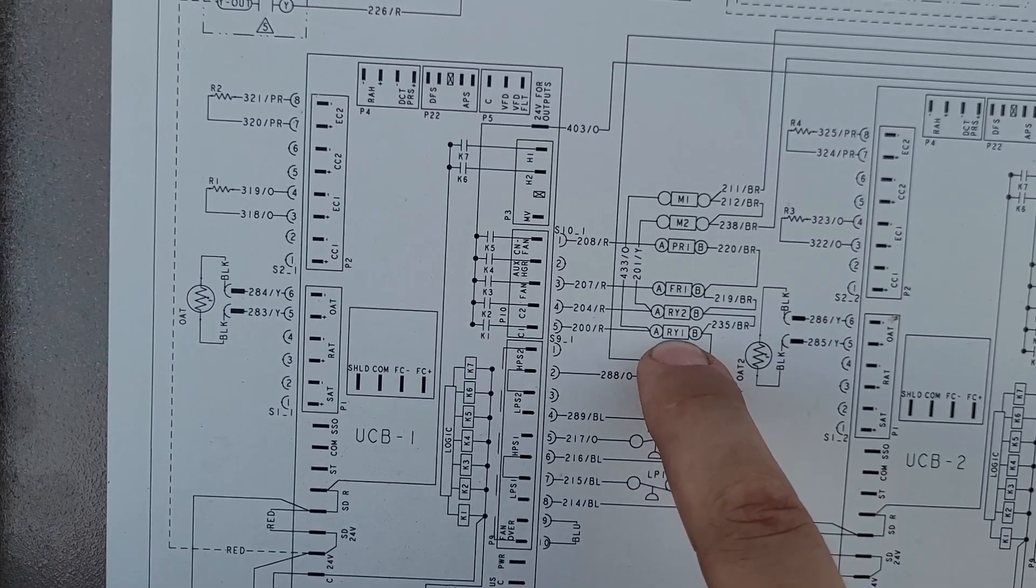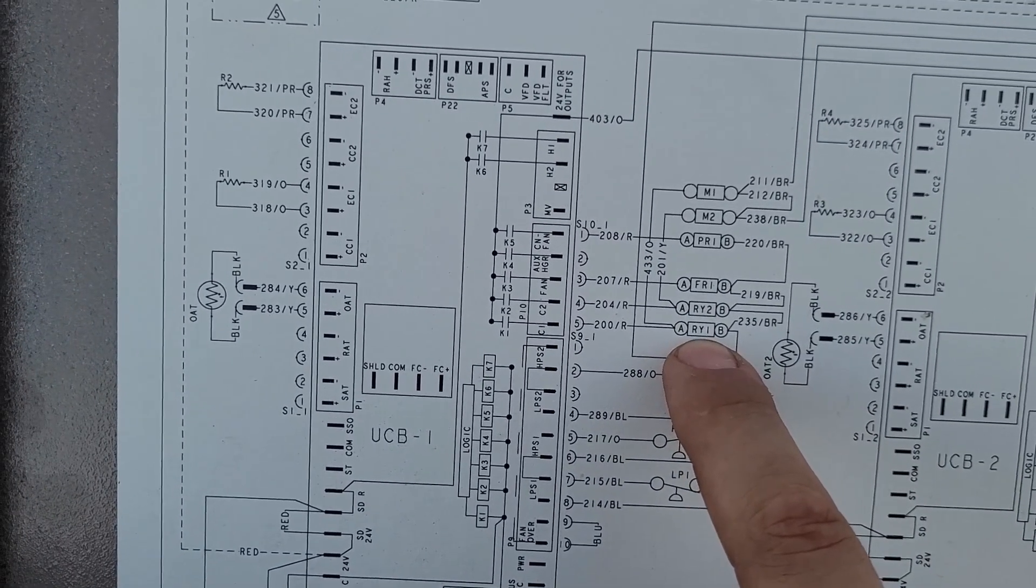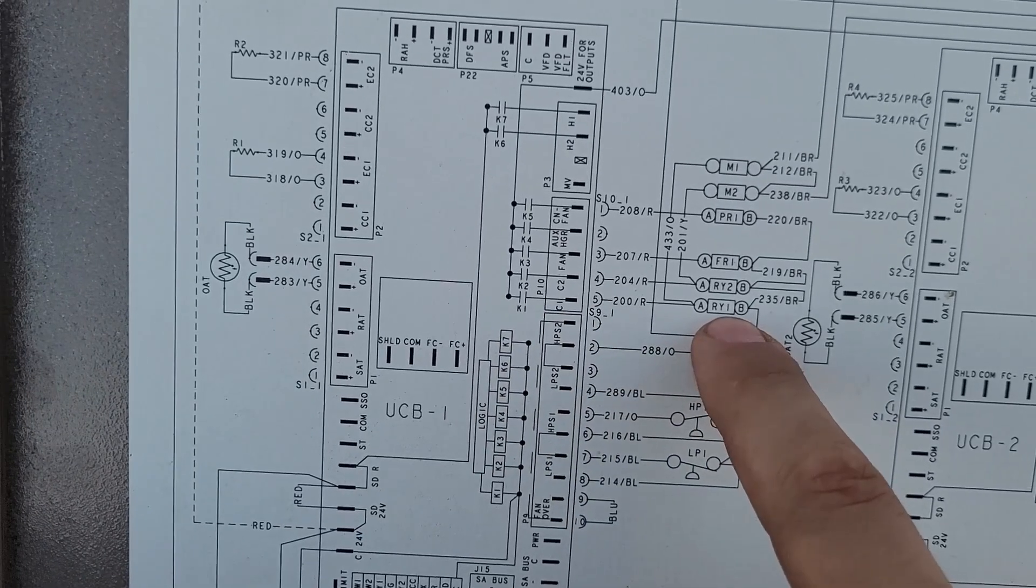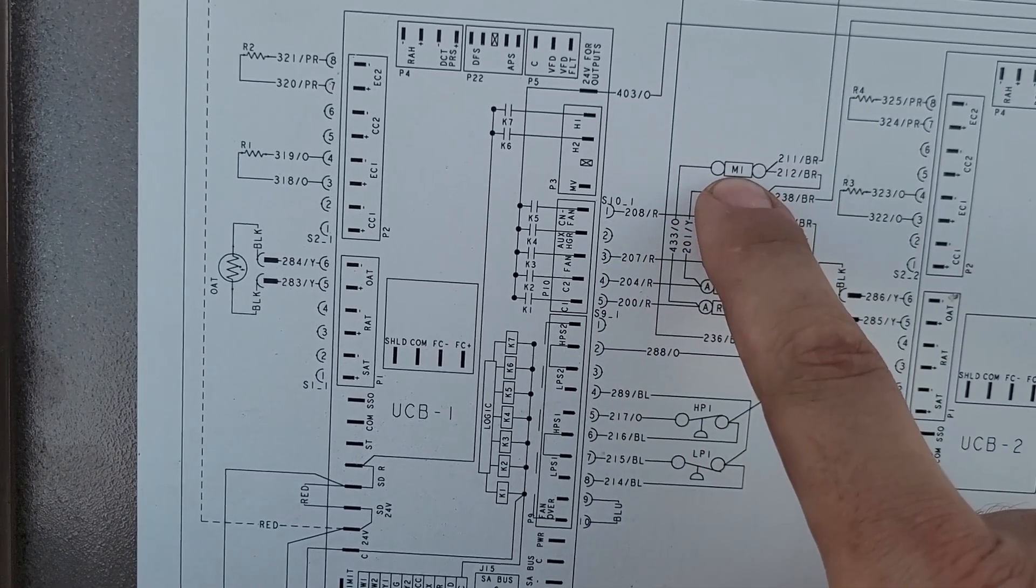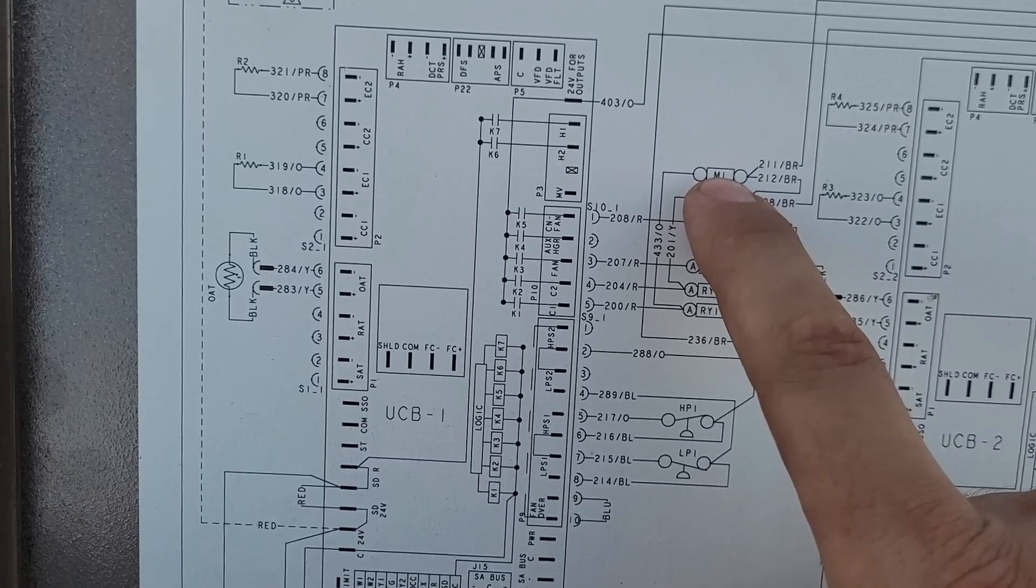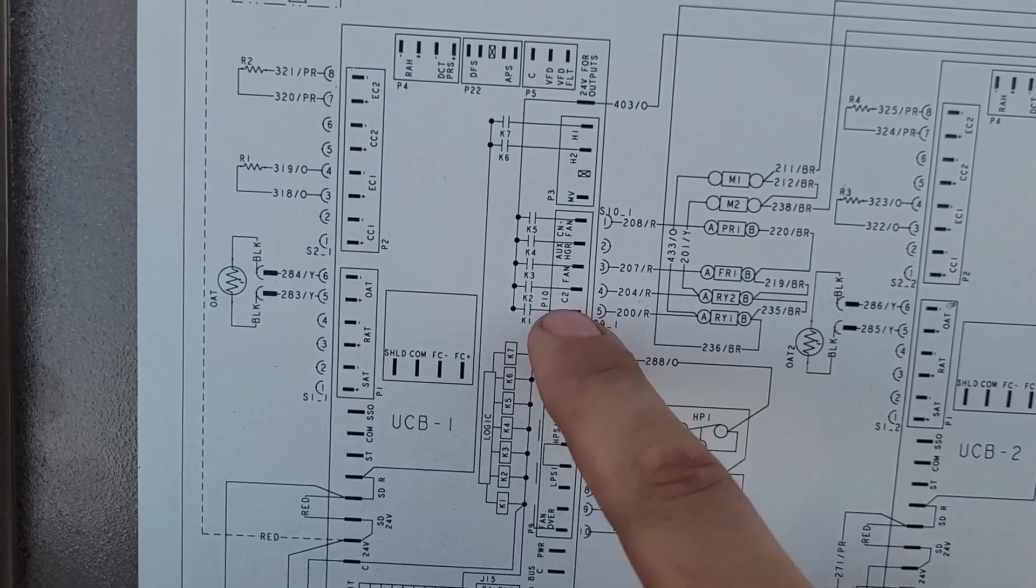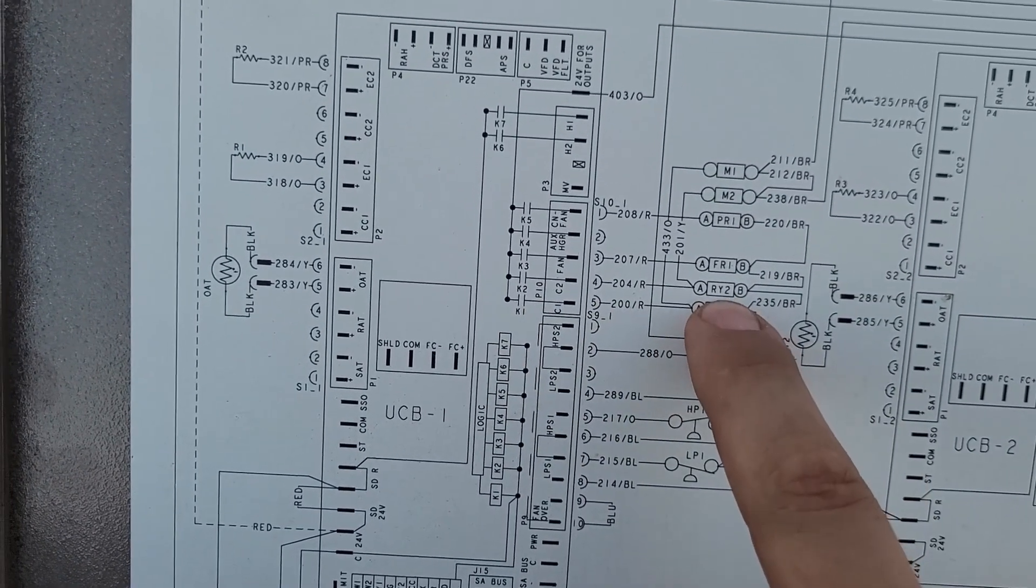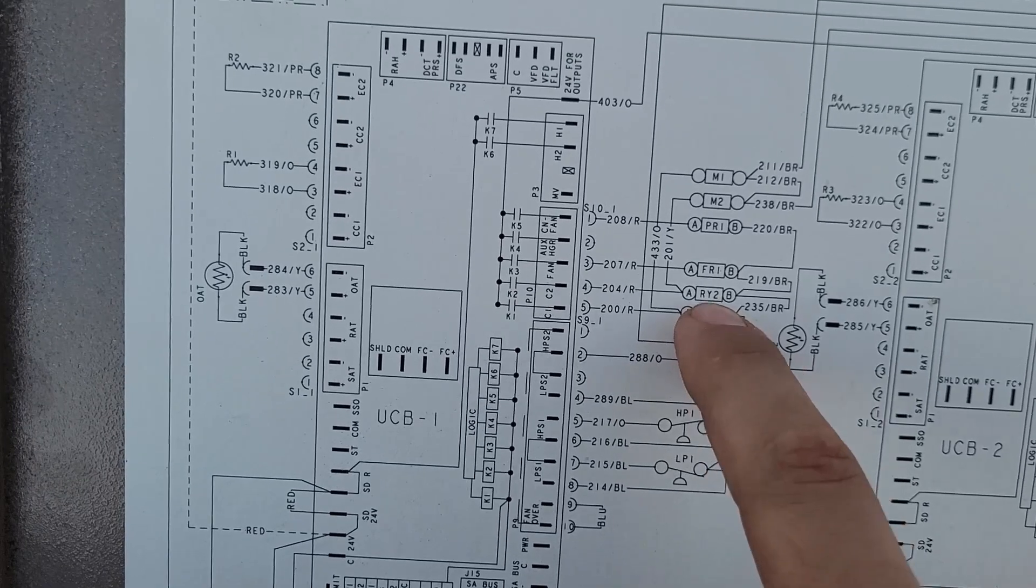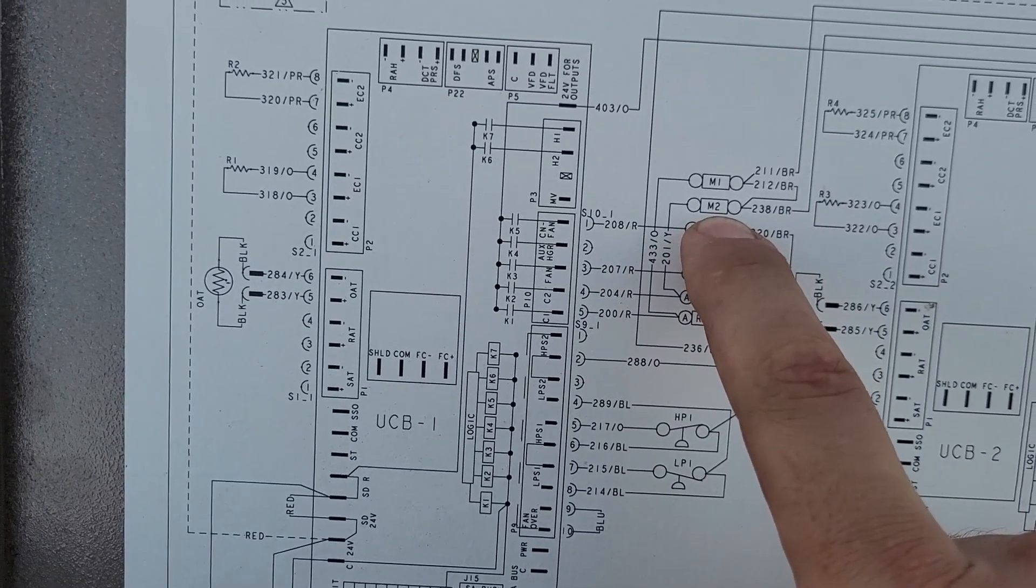And you can see those down here, RY1, the coil for RY1 is there, and it comes from compressor 1, and it also goes up to that, which is having to do with compressor 1. And the same, compressor 2, compressor relay 2, compressor 2.